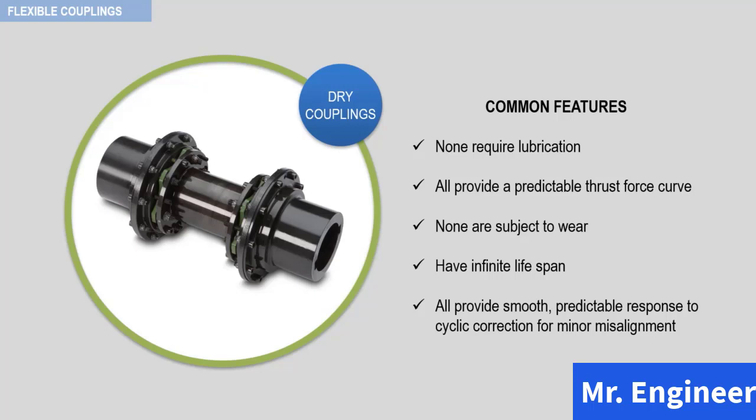All provide smooth, predictable response to cyclic correction for minor misalignment. It should be noted that none of these comments can be applied across the board to gear type flexible couplings. For this reason, more and more special purpose machinery trains are being supplied with flexible metallic element couplings in their design, and many end users do not allow the use of gear type couplings for critical applications.